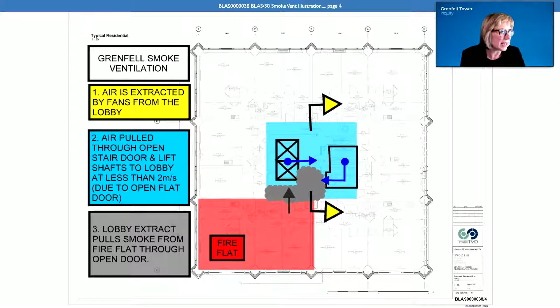First, in the yellow arrows, we see that smoke or air is extracted by fans from the lobby at the north and south shafts, so you've got extraction on both sides. Then in blue, air is pulled through the open stair door and the lift shafts to the lobby at less than 2 metres per second due to the open flat door. And then lobby extract pulls smoke from the fire flat through the open door. Just to be clear, this is showing that when you open the door to the fire flat, because the lobby space is the depressurized space, as well as having the effect of protecting the stair, or trying to protect the stair, you're pulling smoke from the fire flat into the lobby. Do you see that?